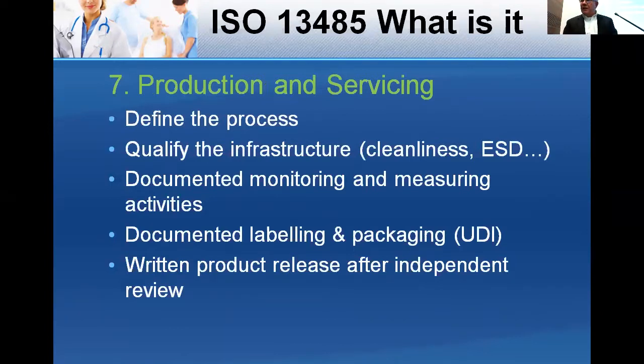Document your monitoring and measuring activities. If you're going out to service a product and it needs calibration, the unit you're using to calibrate with better be within calibration, and you better have records of its calibration. The service technician should have a training record they can leave with the customer to show they're trained to service that particular device.